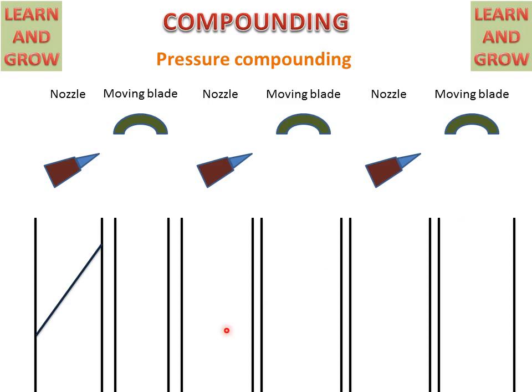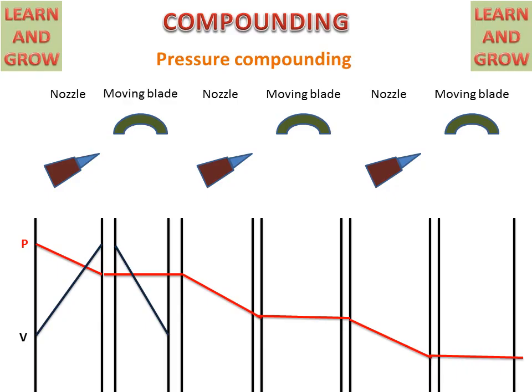In the nozzle, velocity increases and pressure decreases. On the moving blade, pressure remains almost constant. In the next nozzle, pressure further decreases. On the moving blade, pressure is again almost constant. In the third nozzle, pressure decreases, and on the moving blade it is constant. For velocity: on the moving blade, velocity decreases due to loss of kinetic energy. In the next nozzle, velocity increases again, then decreases on the moving blade. This pattern repeats for each stage.